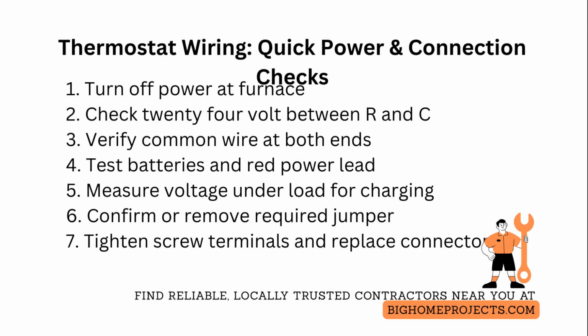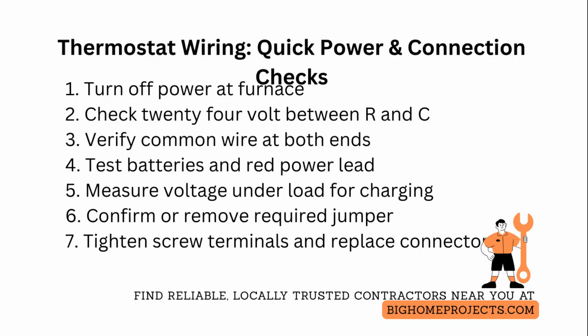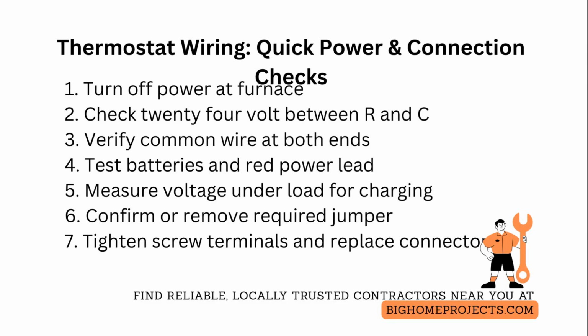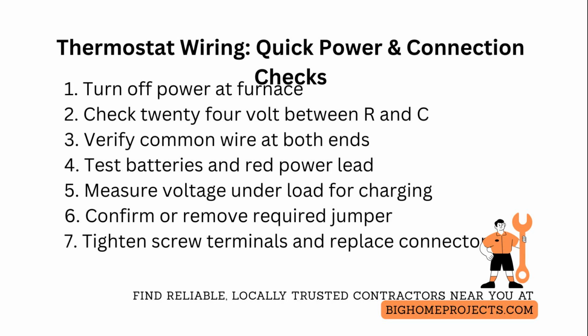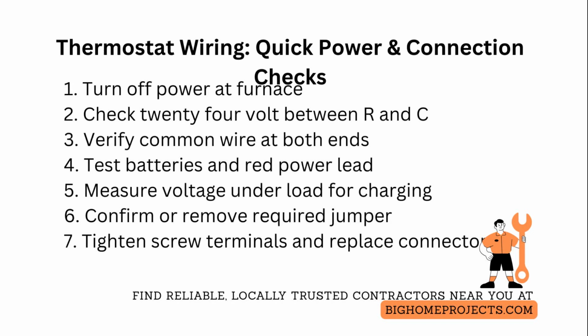If a jumper is required between red and heat or red and fan for legacy systems, confirm it is installed per the manufacturer diagram and removed for devices that expect a dedicated common. Misjumpering can lock out the device. Tighten all screw terminals and, when possible, replace push-on connectors with screw terminations. A single strand under a screw can break contact and cause intermittent unresponsiveness.